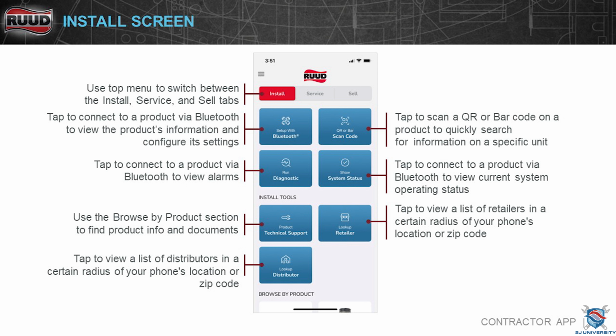So in the install app, I finished my install. Now I'm going to connect to the unit. I'm going to go to setup with Bluetooth. I'm going to jump in that screen, go through and set my parameters on how I want that unit to run. You can also, if you tap in here on this QR code, scan the QR code. There are QR codes literally everywhere on this thing. You can scan the blower motor with a QR code.